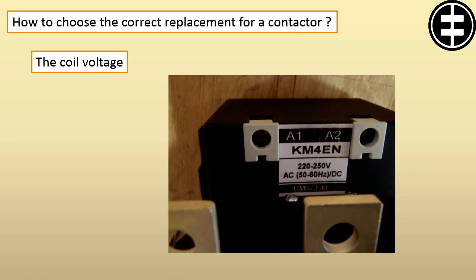How to choose the correct replacement for a contactor? First, you have to check the coil voltage. It is the control voltage which is used to energize the contactor, and you can find it printed on the contactor between A1 and A2. It must be the same as the used contactor.